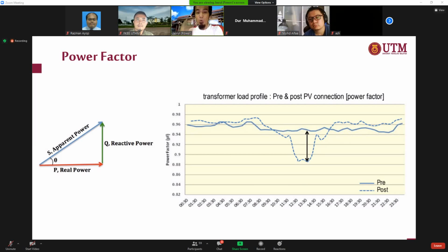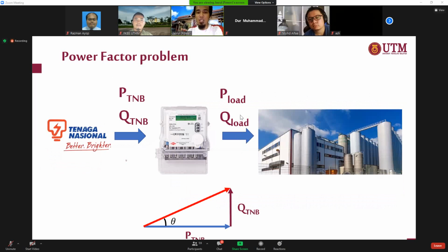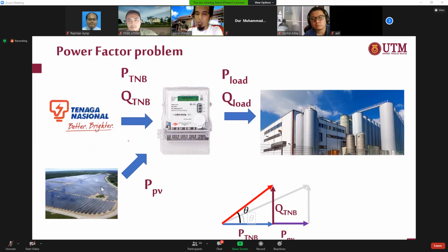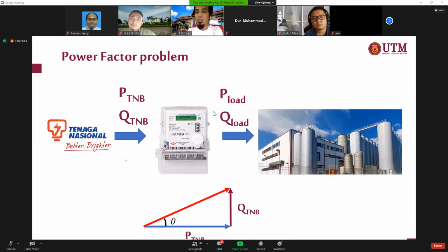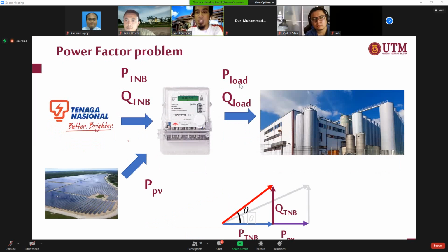What actually happened? I will explain to you why this condition can happen. Let's say in our normal factory, we have the TNB supply and we have the meter. The TNB will supply P and Q, and the meter will transfer the P and Q to our factory. So from this P and Q, we have this P, we have this Q, and this is our theta. This is the original without any PV. And suddenly, let's say you get the PV. What will happen? The P load is still the same. We are still using the same P, the same factory, and we did not add a new load. So with the same P and the same Q, the P can come from the TNB itself as well as from the PV.